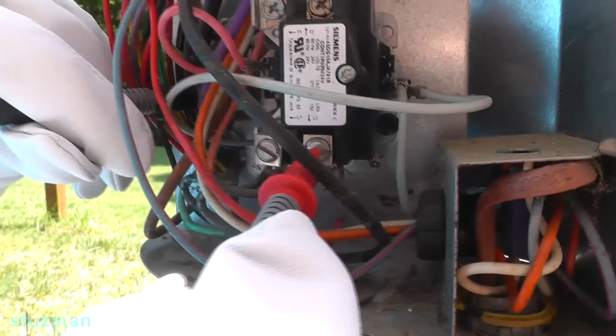Now I'm going to check from one side of the line, and then I'm going to check to the ground, equipment ground - which goes all the way back to the service panel where it bonds with the neutral. So as you see, I have 0 volts there.